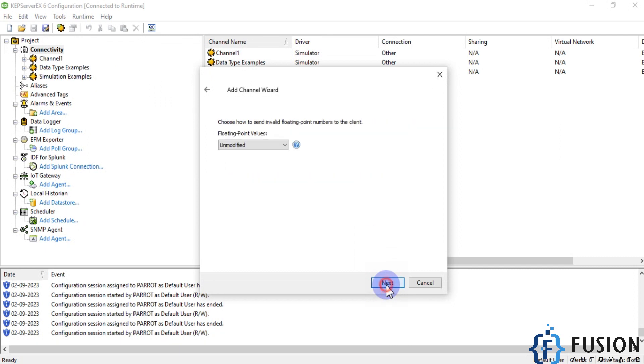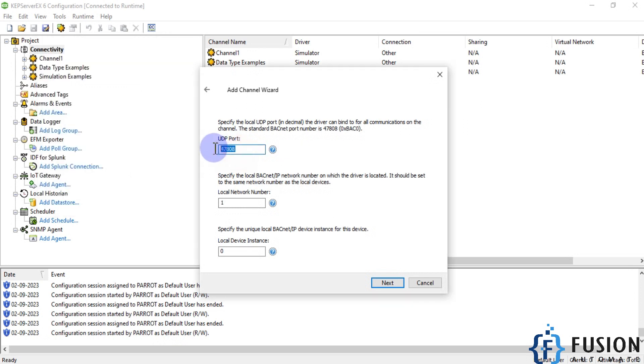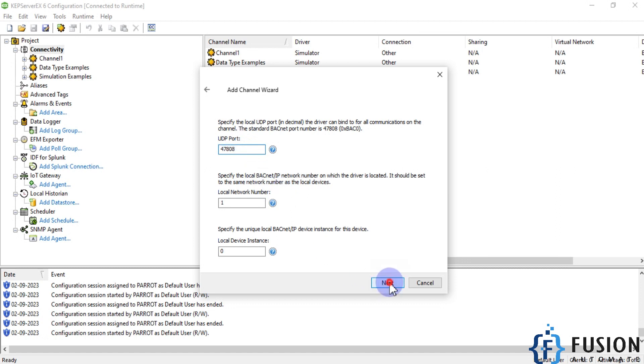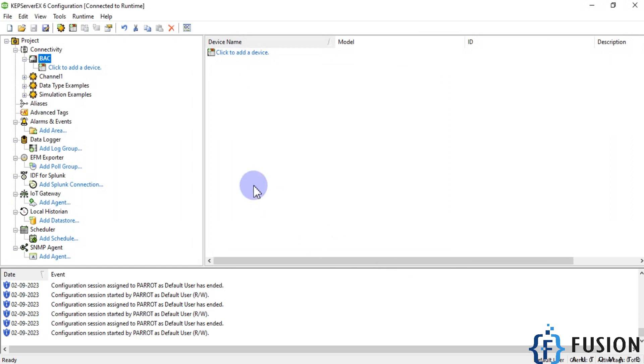Leave the other settings as they are. For the UDP port, this device is running on port 47808, which is the standard BACnet/IP UDP port, so I specify 47808 here. Then press Next and Finish. We have now configured the BACnet channel.